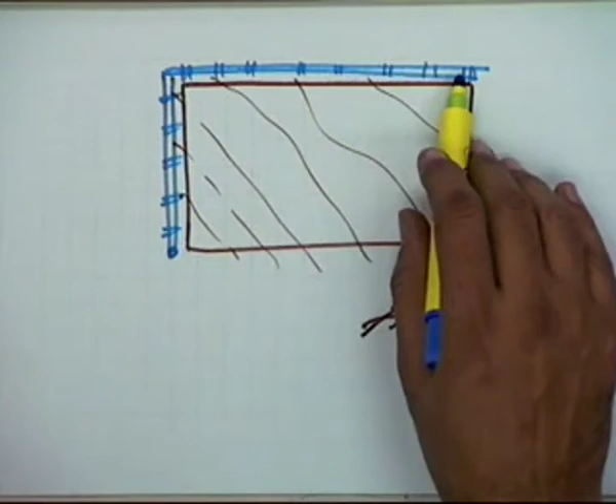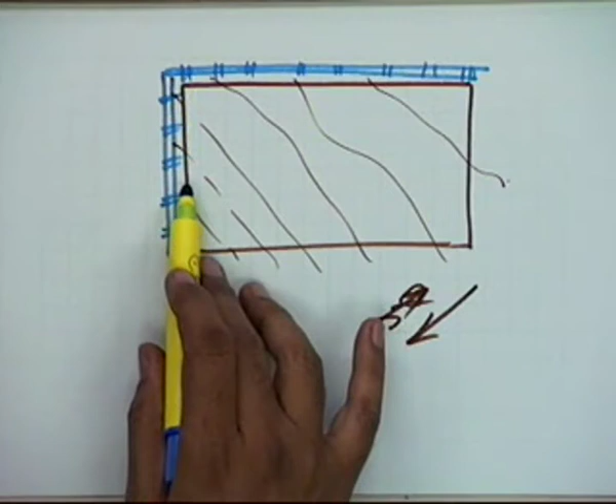Now that might create a situation where the pressures here might be quite within the range, but the pressures here in this zone will become very excessive than what is required. And that is another problem, that if you try to cater to the pressures of the remote areas, the pressure just near to the pump will become very highly excessive, which are much more than what is desirable. So you will have to either go in for pressure regulators at each point of these mainline junctions with the lateral. That will be very expensive affair.